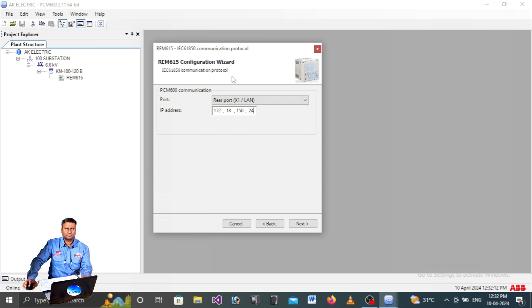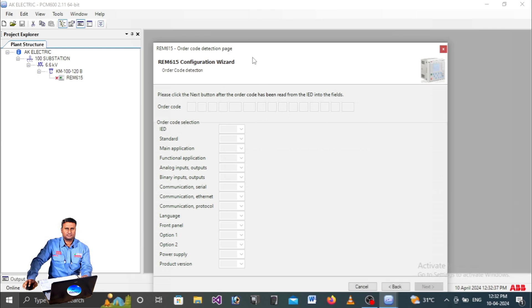Whoever wants to communicate with the relay must check the IP address. In the relay, under the configuration menu, you will find front port and rear port options. Get the IP address from the rear port. Click Next, and if you see an error here, it means the laptop and relay are not communicating. We need to check why communication is failing.